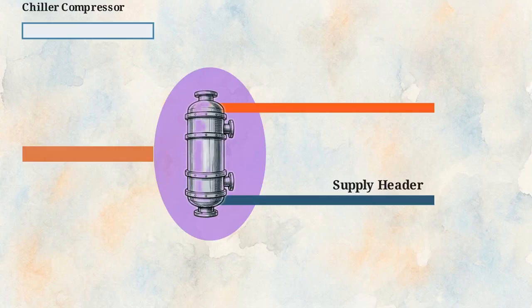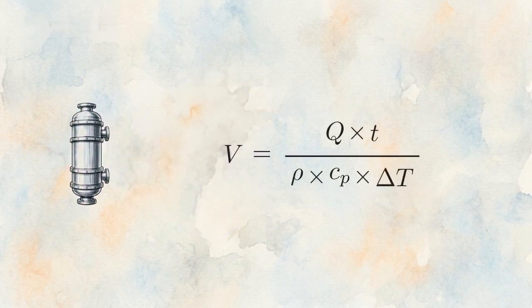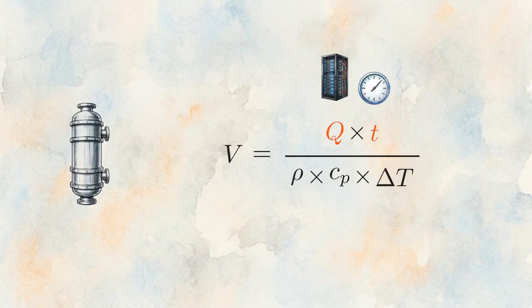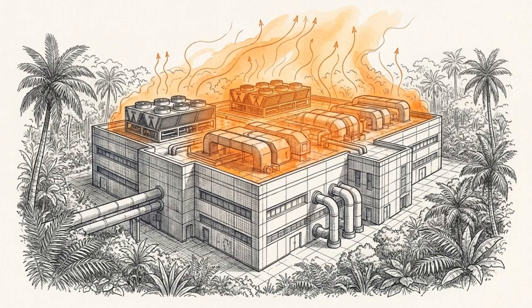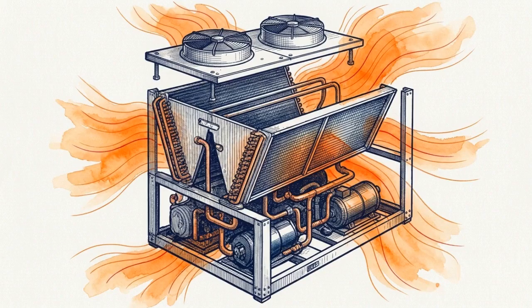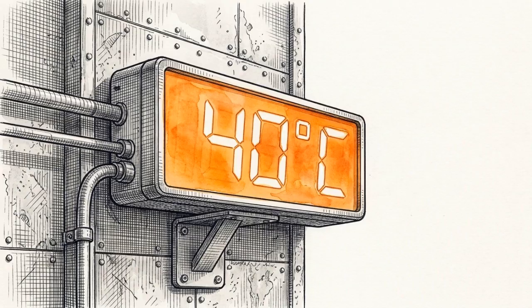Sizing this tank is dictated by hard physical variables: the total protected load, the target time required for the chillers to recover, the density and specific heat of the fluid, and the maximum allowable temperature rise in the data hall. Operating in a tropical climate introduces a severe complication to this timeline. The plant must navigate the physics of rejecting massive amounts of server heat into an outdoor ambient environment that already sits at 40 degrees Celsius.